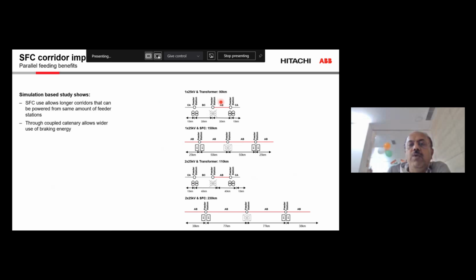Due to time limitation, I will not get into the full details, but suppose we have a 90-kilometer corridor. We envisage around 2 stations with a distance of approximately 60 kilometer feeding on either side, and the distance can be increased to say 150 kilometer, which means between 100 kilometer we don't need any feeding station. So the overall network voltage profile can be increased. At the same time, the distance is also increased without any neutral section. So the overall efficiency of the traffic movement can easily be 1.5 times or more with the same infrastructure, by just replacing the normal substation with the SFC substation.